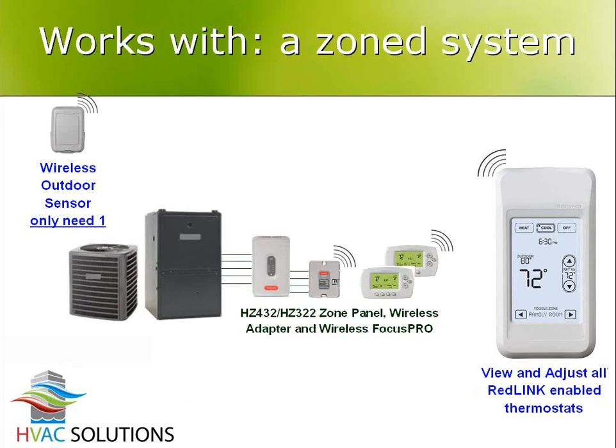If I go to a zone type system, once again, portable comfort control is wireless, outside air is wireless. I have one equipment module that's talking wirelessly to my zone stats, in this case 2 zones. And my equipment module is physically wired to my zone panel, which is physically wired to my furnace, which is also wired to my dampers. So it's wireless from the stats down into the mechanical room, but in the mechanical room it's hardwired. And that's okay because there's not a real difficult time wiring within the mechanical room to the dampers and the panel and everything. The problem is the thermostats up on the second floor and getting wires down to the basement. That's the part you need the wireless for, and that's where this guy solves those kinds of problems.